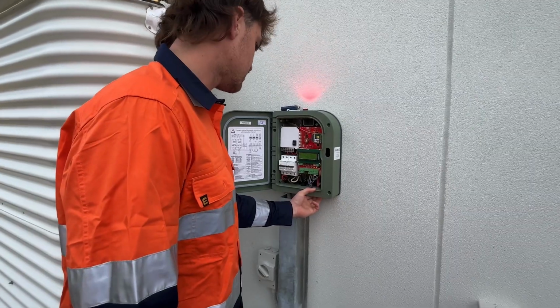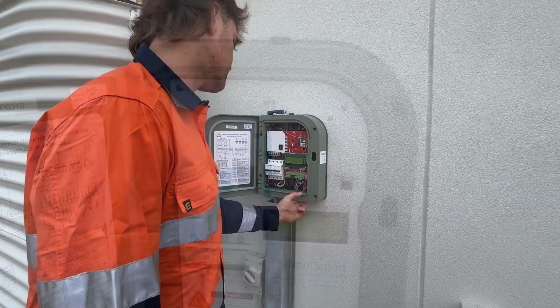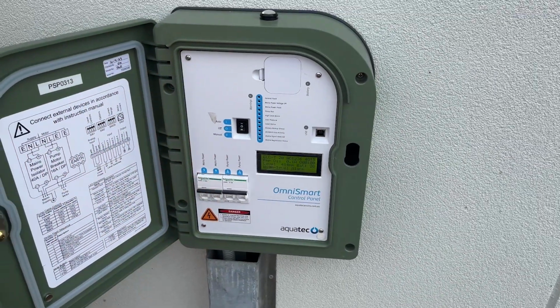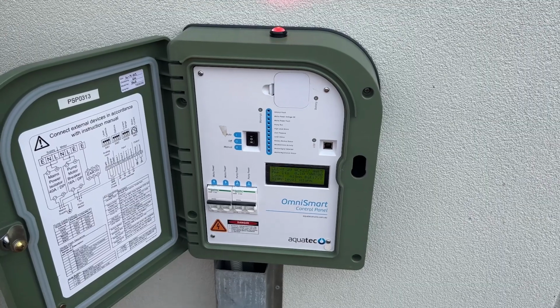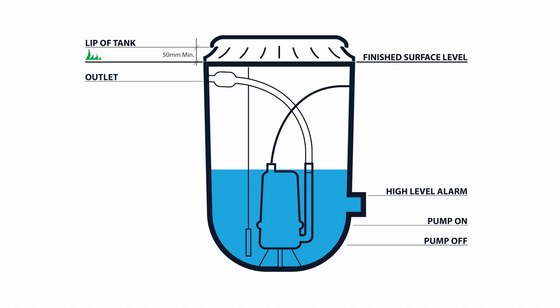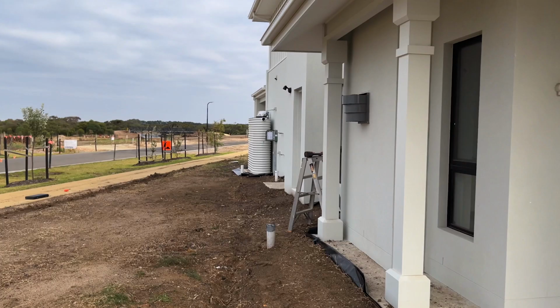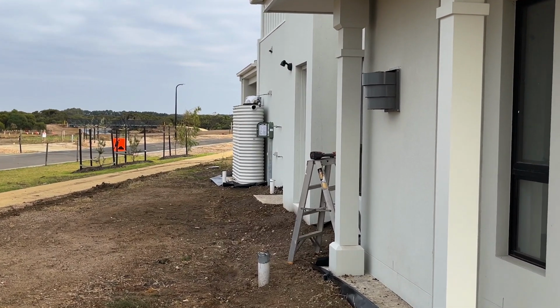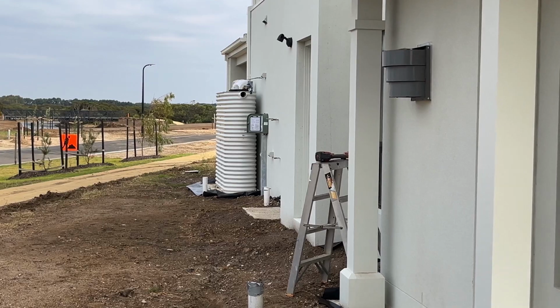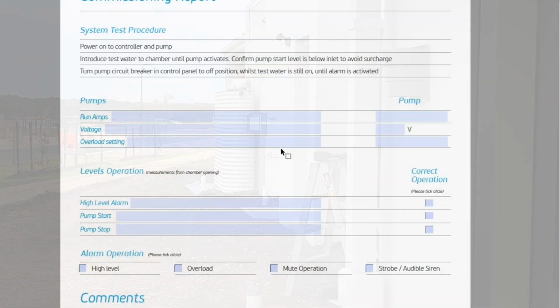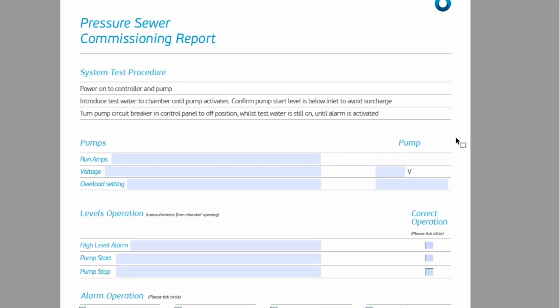Now we can turn the test water off once we have it up to the desired level, and we've also confirmed the alarm's activated and in the right spot. Turn the test water off. Turn the pump back on and watch the water pump out of the well. The pump should then continue pumping, depending on your control panel type. You can monitor and record the running amps at this point in time. Document this information in your commissioning report.